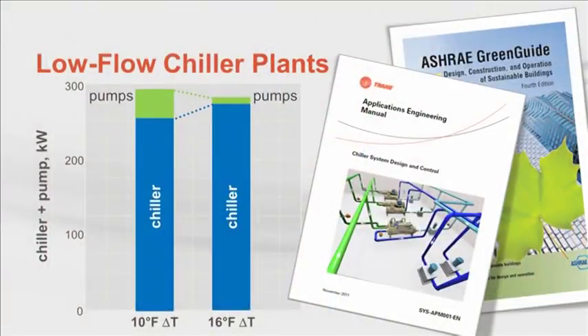The important thing to consider is the overall plant energy efficiency. Although you don't necessarily have to use colder water to get a higher DeltaT, it may be the best option in some cases. If the chiller is producing colder water, it will use more power, but in many applications, the overall energy used by the chiller plus pumps will be less. That's why many in the industry, including ASHRAE's Green Guide, recommend designing chilled water systems for lower flow rates or larger DeltaTs. We've listed several resources on low flow designs in the bibliography in your handouts.